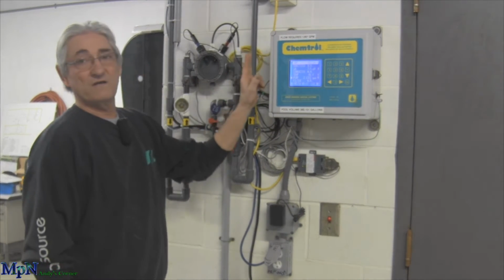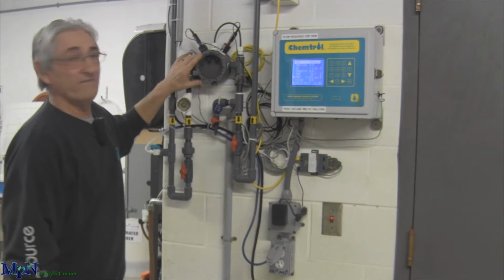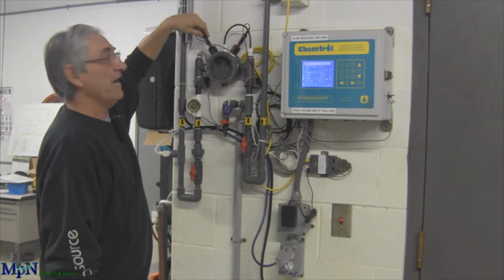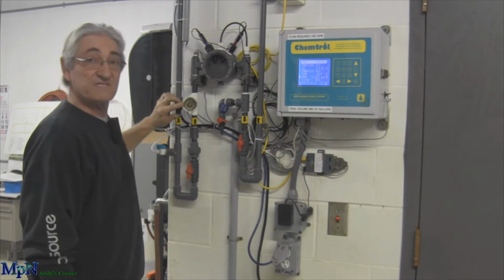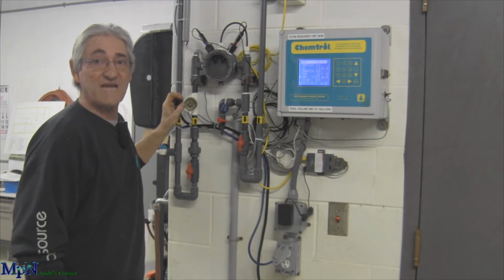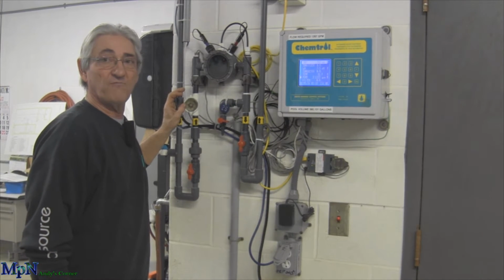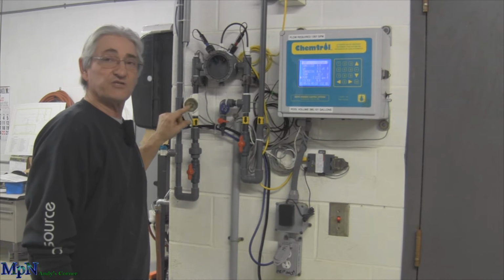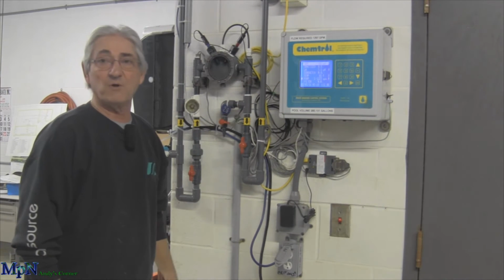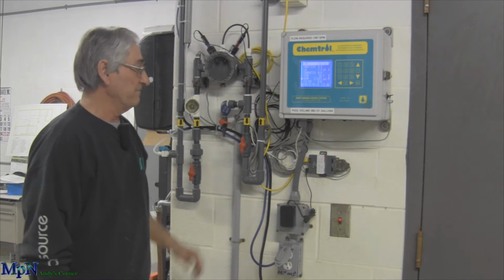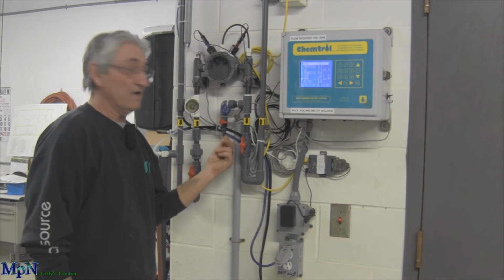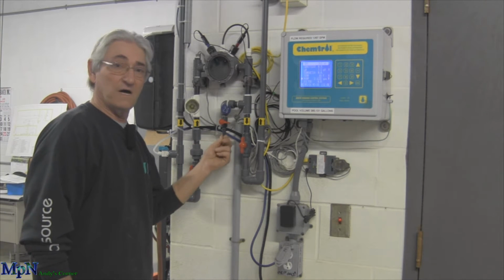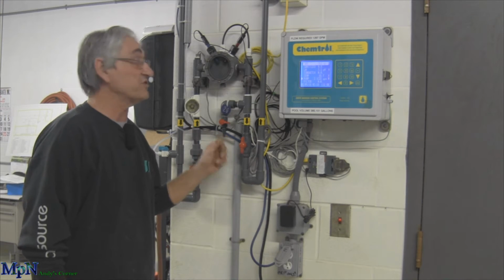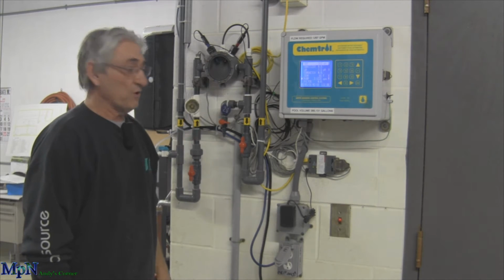The components are the controller. We have a flow cell with the ORP and the pH probe. We have a safety flow switch, so if the flow stops from shutting the pump off or a power failure, this unit will stop the feeding of any chemical, chlorine or acid. We also have a sample cell, a valve in order to test the water, to check what's going past the probes.